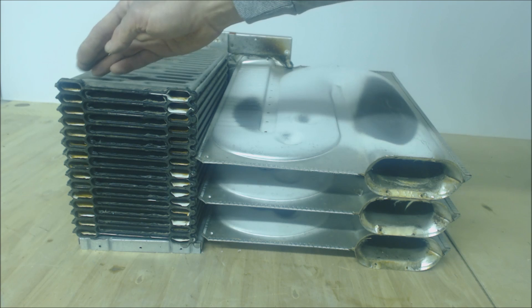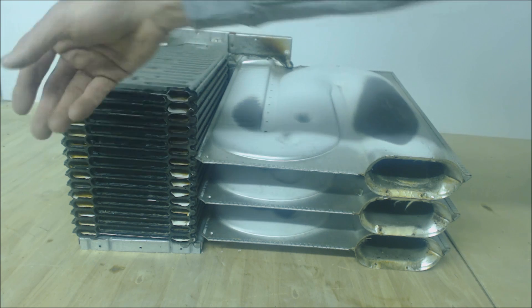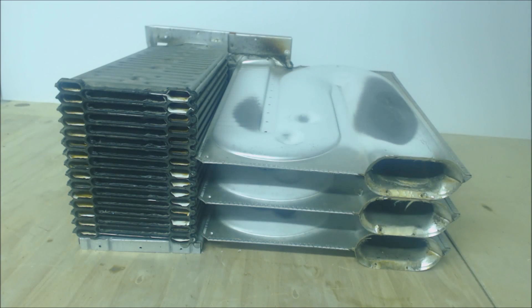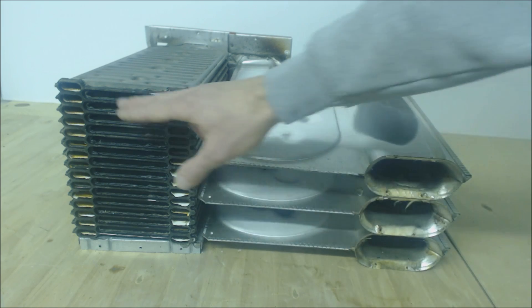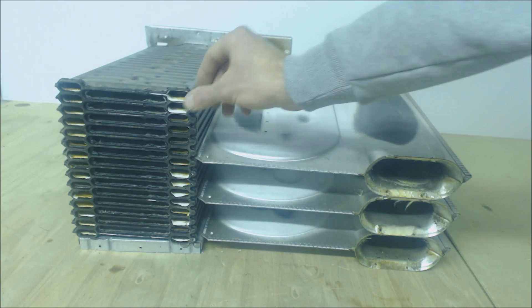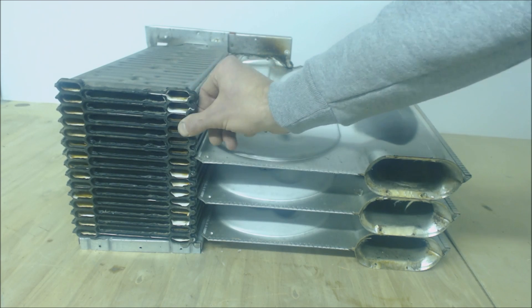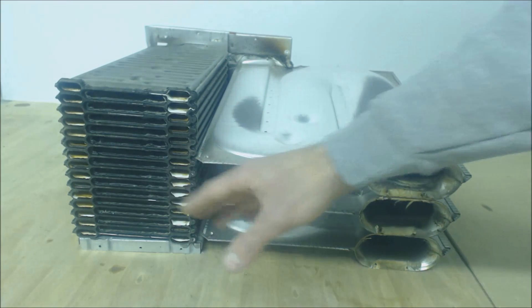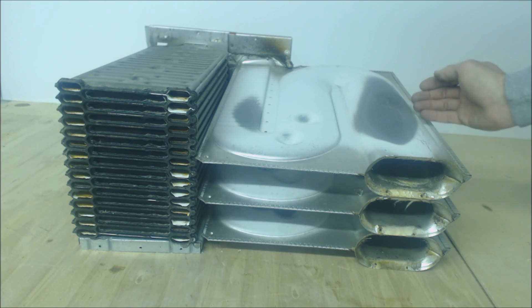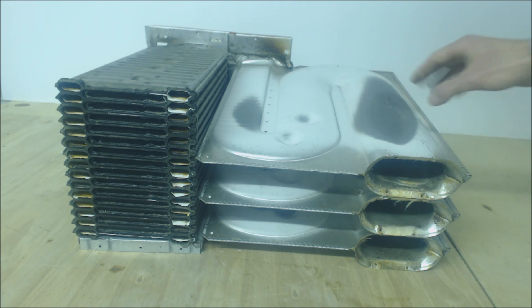This side looks pretty good. This is where the inducer motor connects with gasketing material, and that all looks good. This area is pretty good. There's no cracks in the heat exchanger over here in the primary heat exchanger.